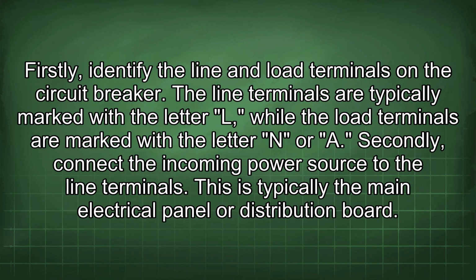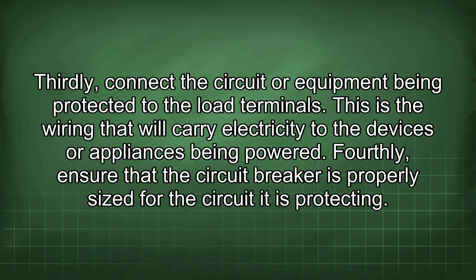Firstly, identify the line and load terminals on the circuit breaker. The line terminals are typically marked with the letter L, while the load terminals are marked with the letter N or A. Secondly, connect the incoming power source to the line terminals. This is typically the main electrical panel or distribution board. Thirdly, connect the circuit or equipment being protected to the load terminals. This is the wiring that will carry electricity to the devices or appliances being powered.